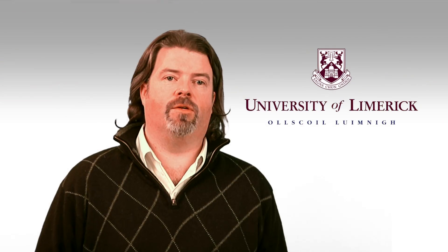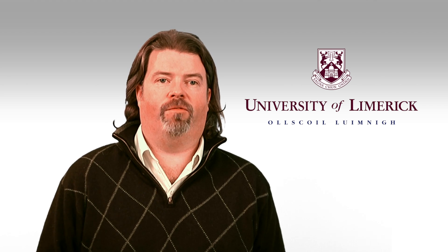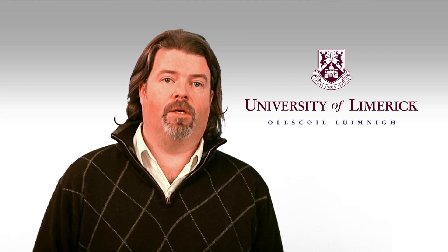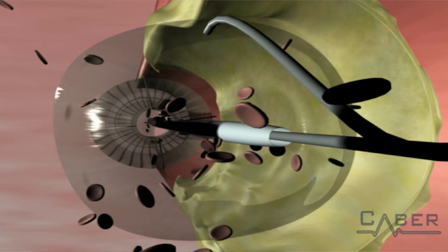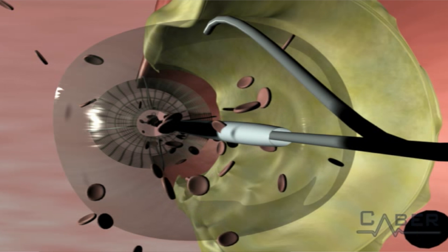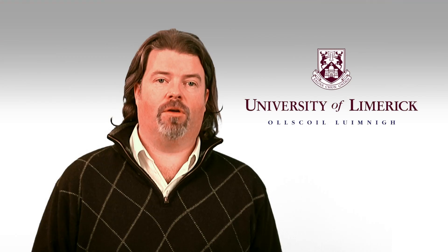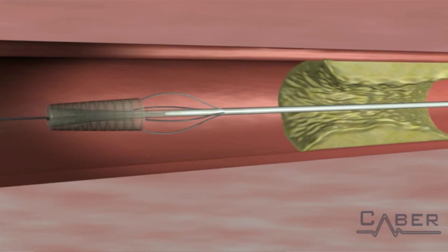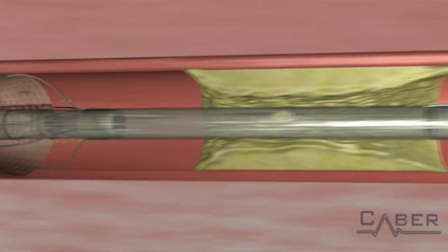When deploying this device, it does not have to be inflated and deflated in a cyclic manner. It can just be inflated and left in place for a timeframe to be determined by the consultant. It also allows cranial perfusion throughout the deployment of the device because it has a hole down through the centre of it. It has a filter attached which is a novel design, also used to filter blood that comes in contact with the plaque during any stage of the deployment or retraction of the device.